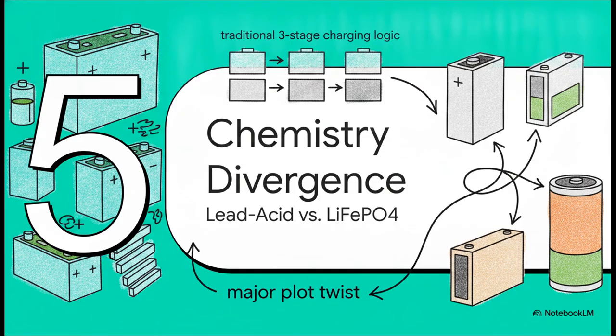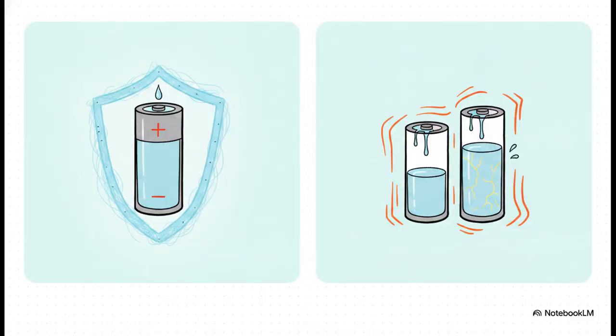Now for Section 5, the chemistry divergence. Lead acid versus LiFePO4. All right, up until now, everything we've talked about basically forms the holy grail of traditional battery charging. But here is the major plot twist. Let's look at this side-by-side chemistry divergence. For lead-acid chemistries, like FLA, AGM, or gel, everything we just learned is 100% mandatory. They have to return to 100% regularly, and they rely heavily on that continuous float voltage to stop sulfation.